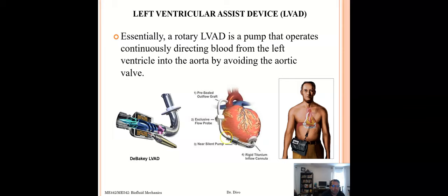Now, this picture here is of the DeBakey LVAD. It's one of those state-of-the-art pumps that is used nowadays. There are a few companies here in the United States and in Europe that fabricate these pumps. There's the HeartMate and the HeartMate 2, which is very pervasive in the medical market. These are very similar designs. But this is one of the first ones that was conceived to be an axial flow, continuous flow pump.